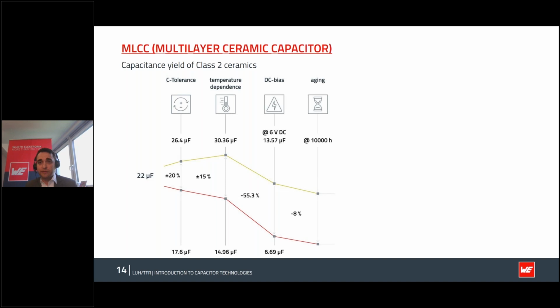So after all these effects combined, out of the 22 microfarads you used to have, in the best case, you have about 12.5 microfarad, so close to half of the initial value. And in the worst case, you're down to 6.15 microfarad, which is pretty much a quarter of the initial value. You can use them like this, but you do need to make sure that you actually calculate all these effects to have a good safety margin in there. Otherwise, you might end up having a capacitor with not enough capacitance after some time.